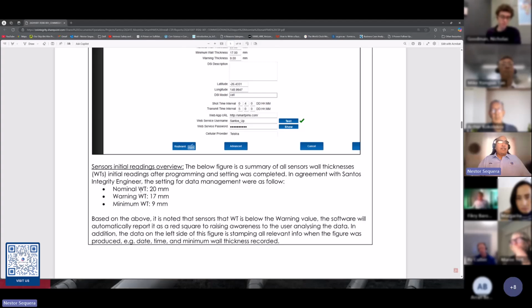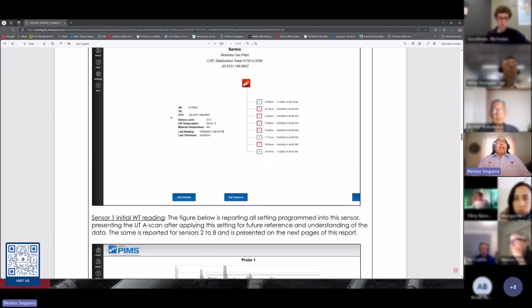For the client's vessel, for instance, it is 20 millimeters nominal wall thickness. Then we put a warning wall thickness, which is 20 minus 3 millimeters corrosion allowance. So the warning is 17. And the client also told us that the minimum thickness that they had calculated for that tower is 9 millimeters. So we've set that already onto the system. Then based on that, we do initial readings, and the software is intelligent enough to highlight already items that are under the corrosion allowance.